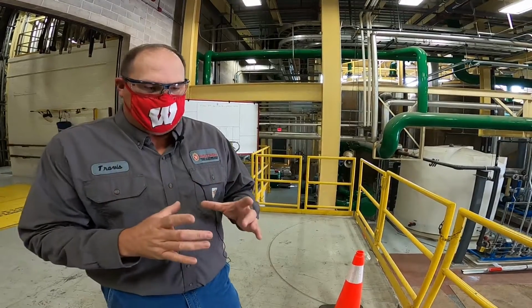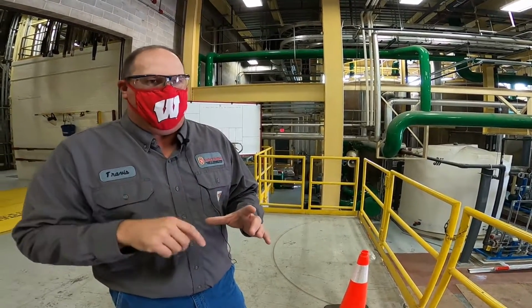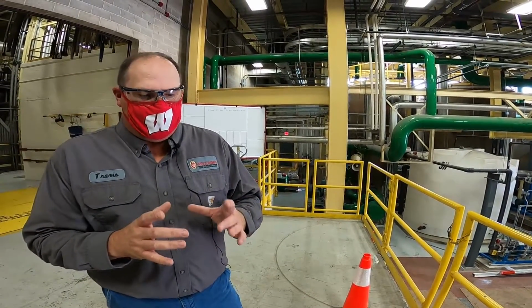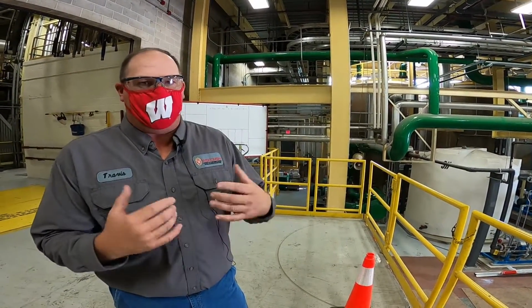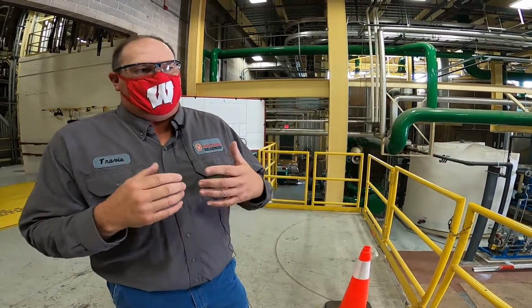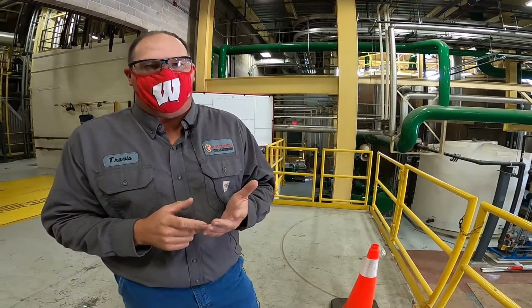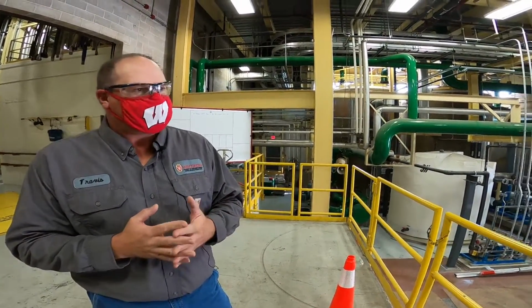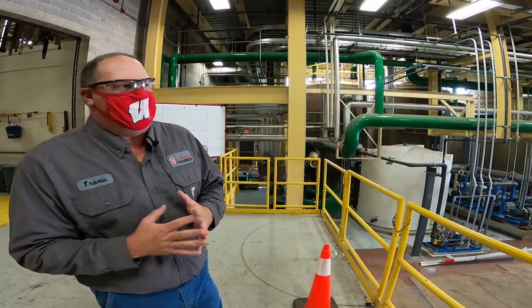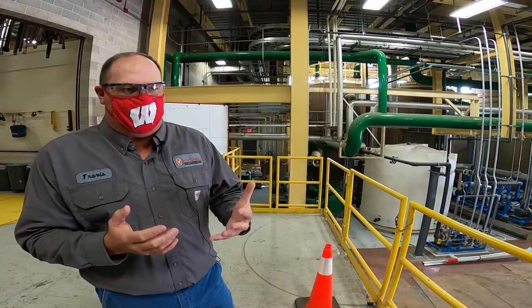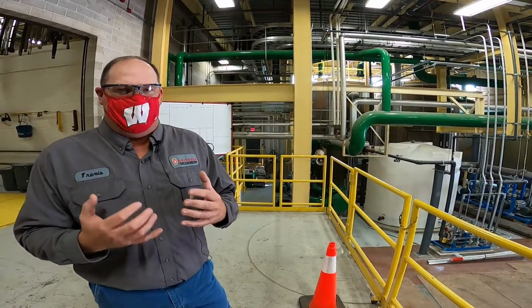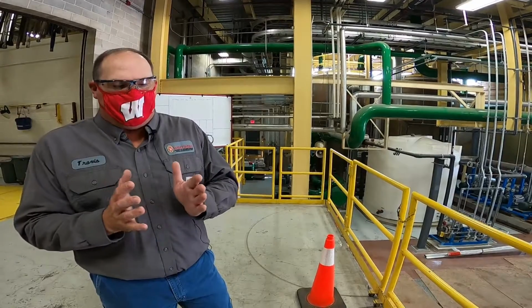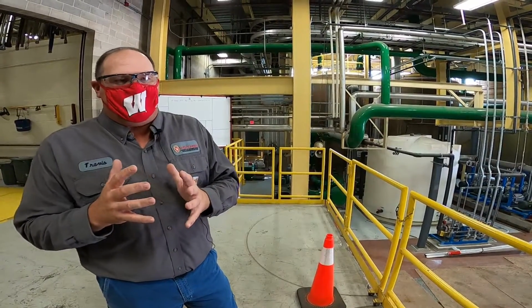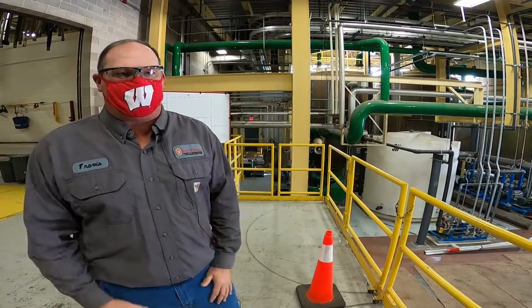Kind of like when you cook noodles on the stove and you have that little ring, calcium ring in the pan after you're done. We don't want that, so we eliminate all that calcium, magnesium out of the water, iron, so it doesn't lay up on the boiler tubes in the boiler. If we don't do that and we allow that to get into the system, we're now going to build scale on the boiler tubes. And what does that mean? Suddenly it's going to cost you 10, 15, 20% more in fuel costs to get the same amount of steam out of that boiler, because you got to heat now through that scale to get that heat transfer across to the water to turn that water into steam.